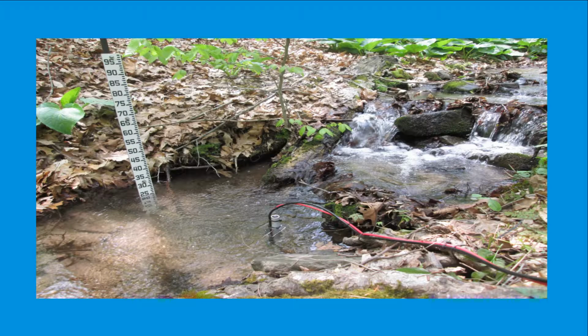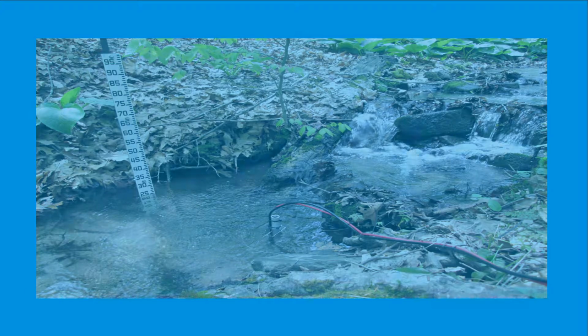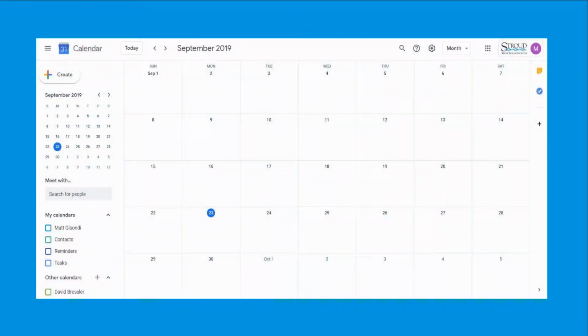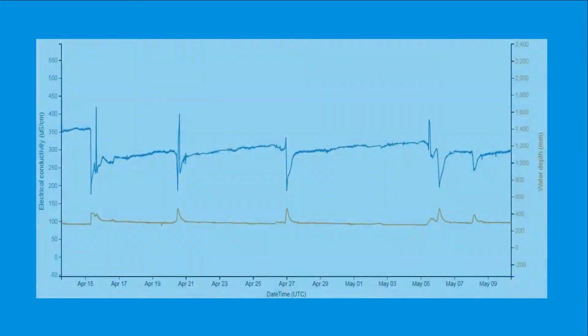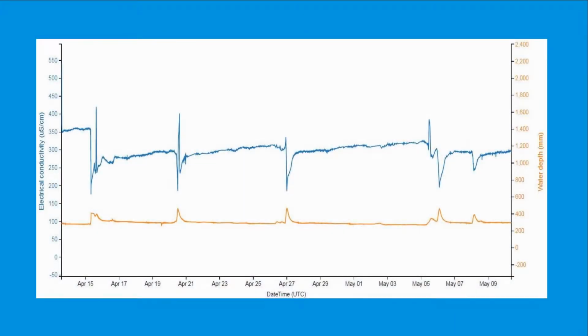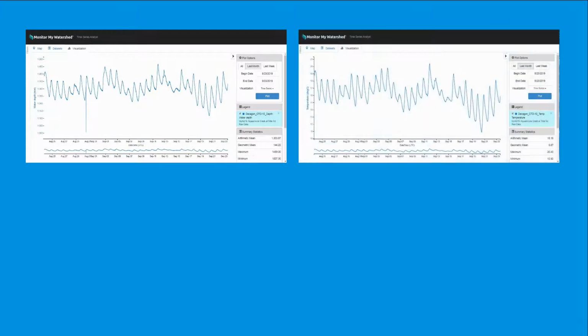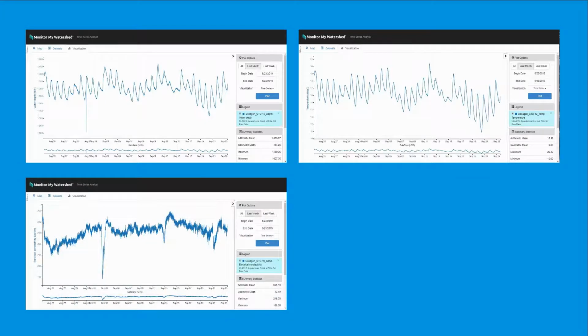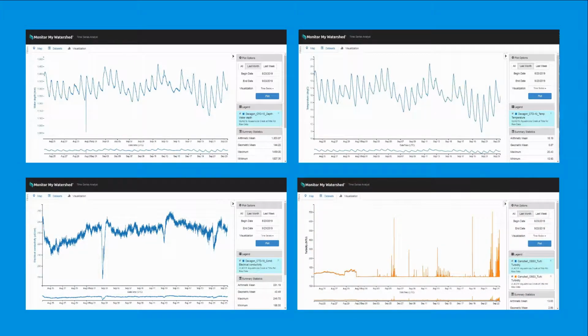Today I will go through the process of carrying out a quality control check of your sensor station. Sensor station quality control should occur on a quarterly basis, or every 3 months within the year, to monitor the quality of the data as well as to provide reassurance of data quality to those who will be using the sensor station data in analysis. The quality control process cross-checks the sensor station's depth readings, water temperature readings, conductivity readings, and turbidity readings with handheld meters and basic tools.